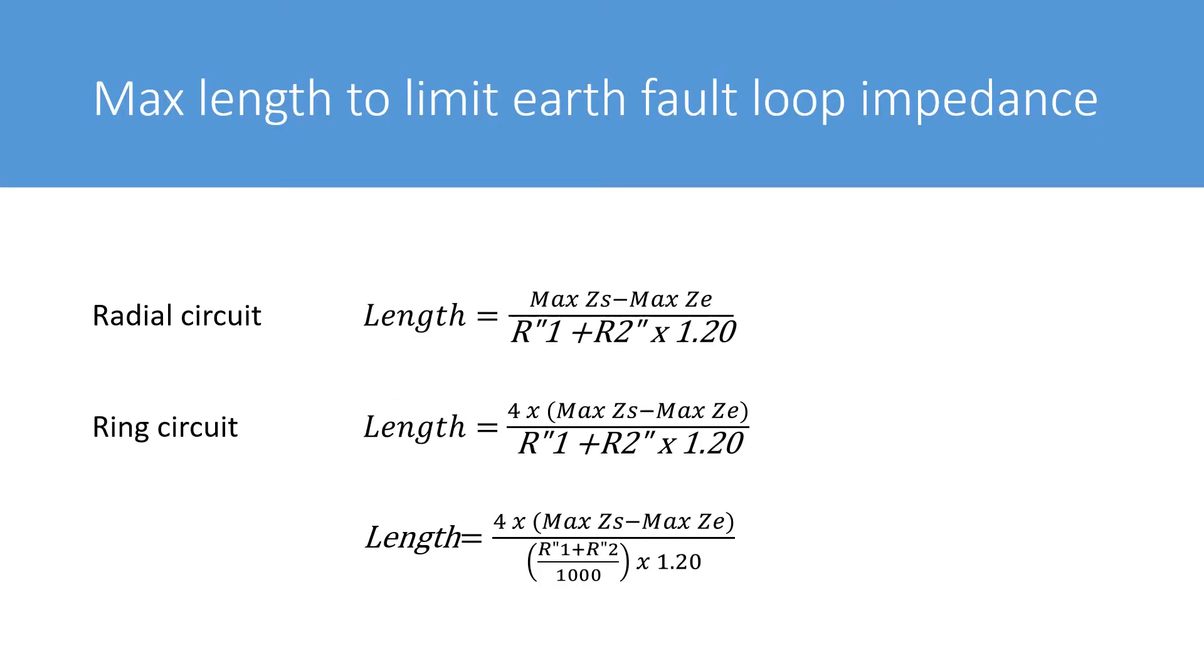So here we have an example of the calculation for the maximum length for both radial and ring circuits. For circuits wired in a ring, when we are measuring to the farthest point of the circuit, it's necessary to add a multiplier of 4 to the equation to allow for the loop of the circuit.